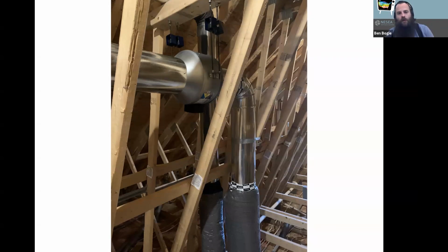I really like remote blowers whenever possible, because I feel you get better performance out of them, and also because we can take the noise outside of the building. We use vibration dampeners, and we're isolated by the flex duct and all the rigid metal, so we're not getting vibration transfer down into the house. One thing to note: the 8-inch round you see there is actually the hood exhaust — that doesn't go through plastic flex, it goes through aluminum flex.